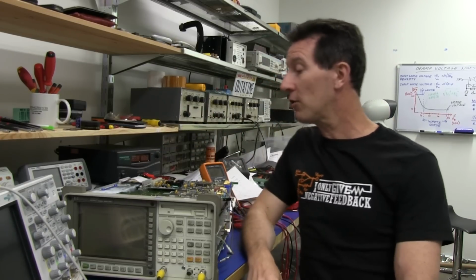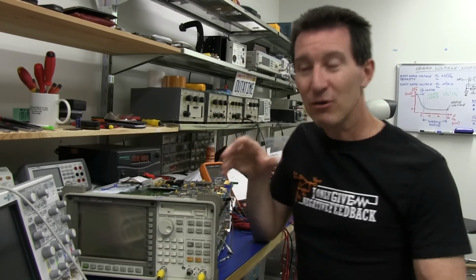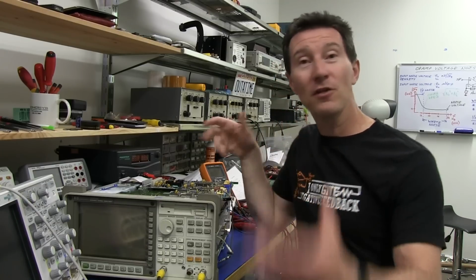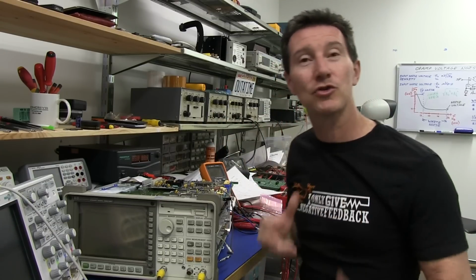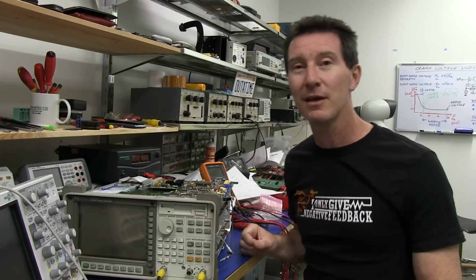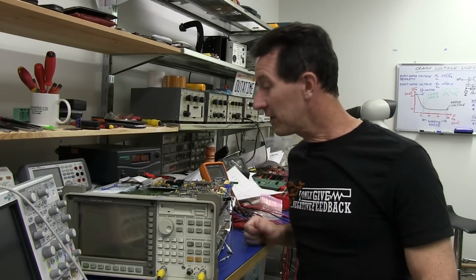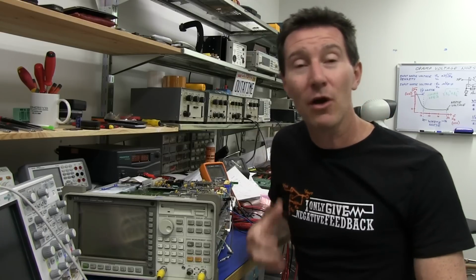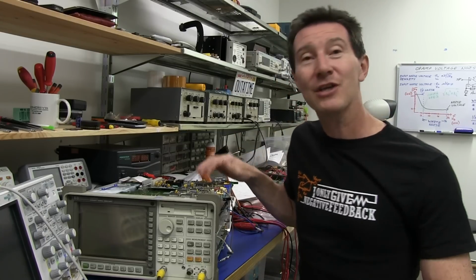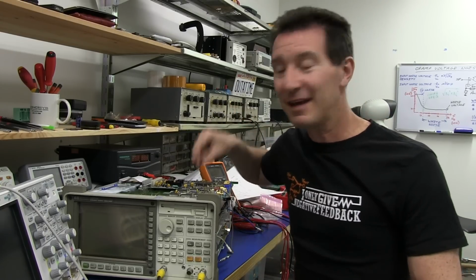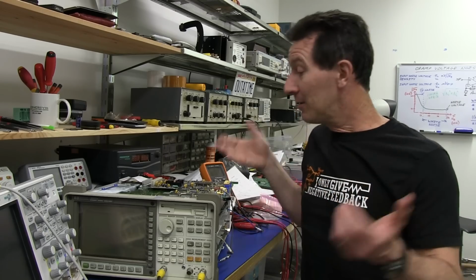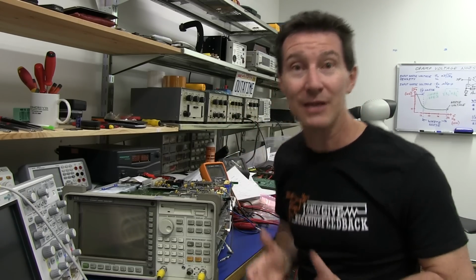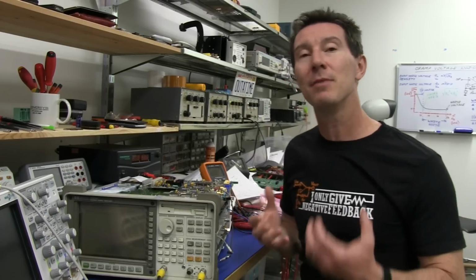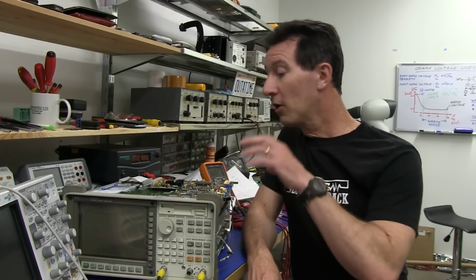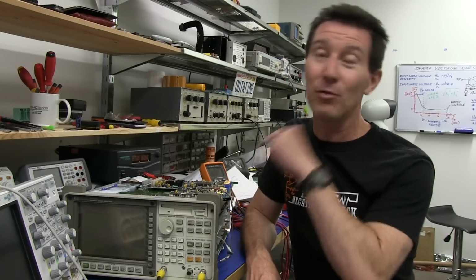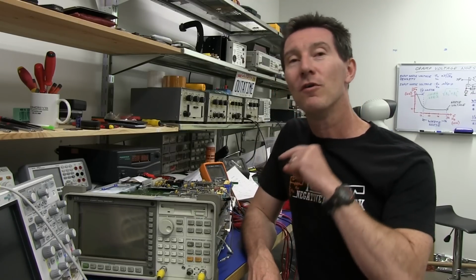These are known faults. So rather than chase our tail, chase red herrings, and follow the service manual for the rest of this thing, that whole 70-page troubleshooting guide, you've got to take a step back, think about this, and go, well, what's most likely to be wrong with this thing? The software tells us there's a fault with the ADC ASIC, but hey, if there's no power going to the ADC ASIC, then you're probably going to get exactly the same error message. So I reckon where I would put my money is that we have more failed voltage regulators on here somewhere.